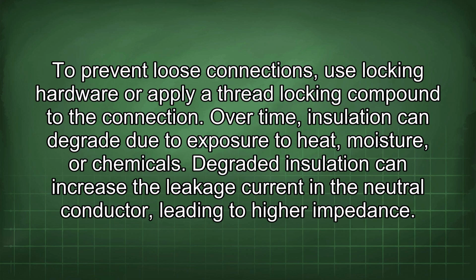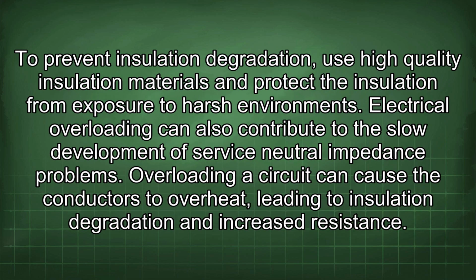Over time, insulation can degrade due to exposure to heat, moisture, or chemicals. Degraded insulation can increase the leakage current in the neutral conductor, leading to higher impedance. To prevent insulation degradation, use high-quality insulation materials and protect the insulation from exposure to harsh environments.